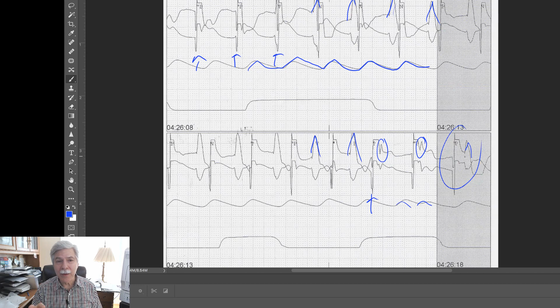So even at high output, this transcutaneous pacemaker was not doing well. You need to be able to recognize when it's working or not. You really need to be able to tell if your therapy is working. And unfortunately, this was not. So it became a real serious problem. Turning off the pacemaker, you can see that the patient now has an escape rhythm, but it's a very slow idioventricular, wide, bizarre looking rhythm at a rate of about 20 beats per minute. So we had a bad problem on our hands.